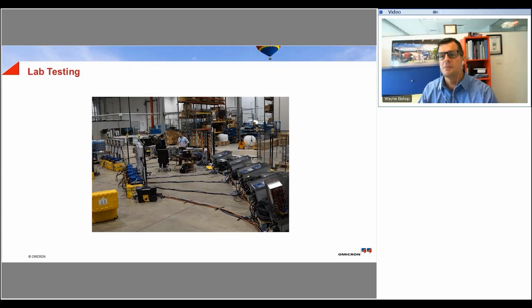This entire process for us took about 3 weeks, from setting up all the equipment, performing all of the testing, testing all of the test equipment, testing all of the individual elements, and then the final customer witnessing of the testing. Fortunately for us, prior to arrival, all of the protection and testing elements were completed, and they were all tested in order to check for any kind of relay failures themselves. So the time that we spent in the lab was purely to verify the protection scheme and the communication logic.